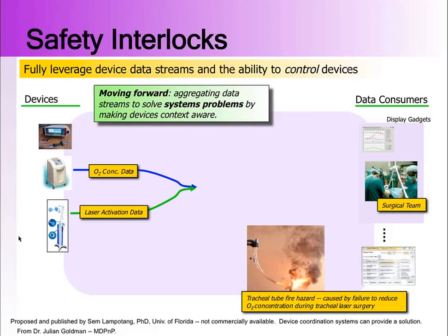So again, if you're able to bring pieces of this clinical space together and control their actions, you're able to do systems engineering and enforce a systems invariant, preventing yourself from getting in the hazardous state where one device is operating with another that it might interfere with.